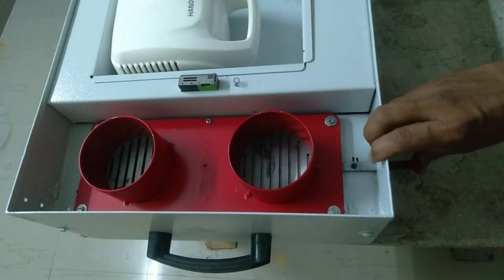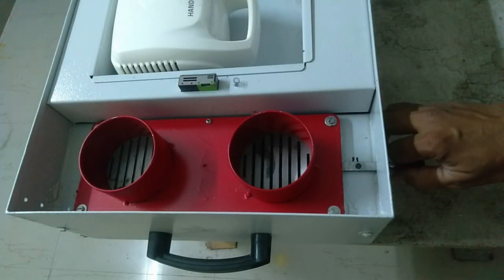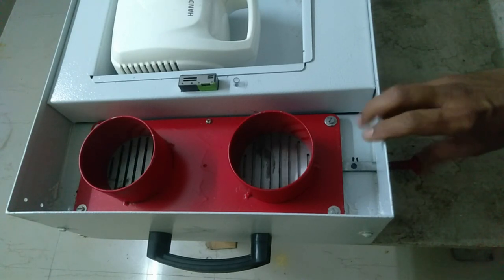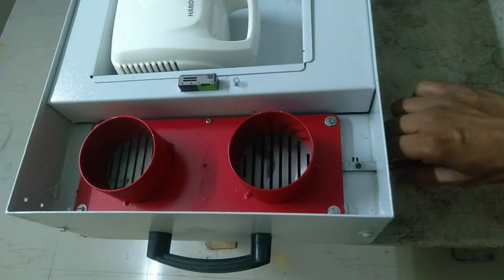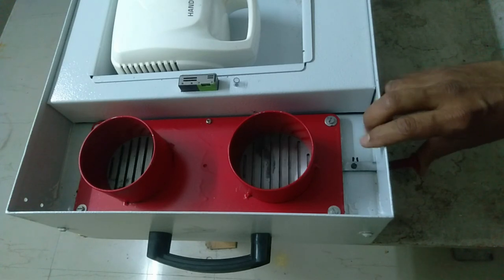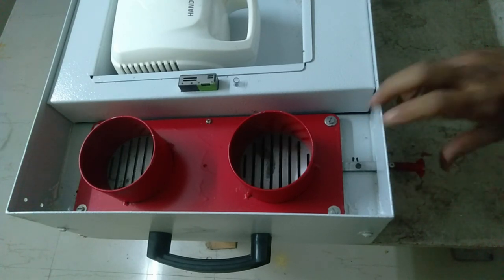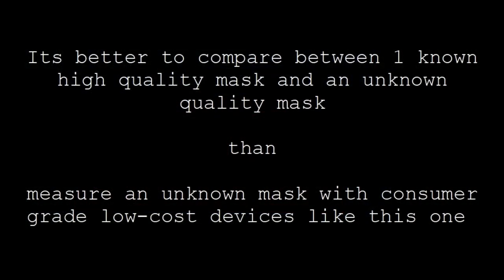A mask selection system has been implemented here. This allows us to select which of the two masks is being tested. When one mask is selected, all air passes through it and no air passes through the other mask. This system allows the masks to be compared to each other while other parameters are held relatively constant.